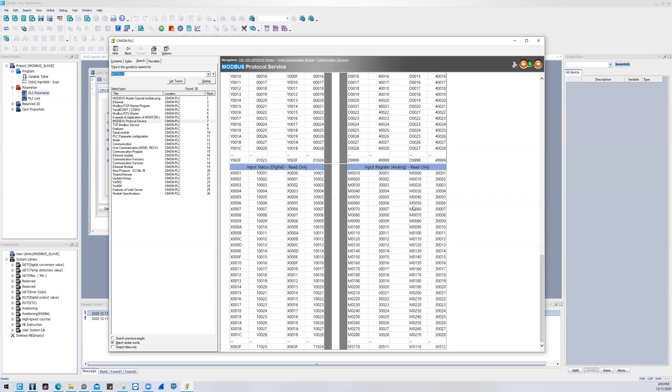The same can be said about your M's. You just have to put a 0 at the end of the register, and that will declare the word form of that register. So if I target 300008, that means I'm looking at the register M70, the word. And notice how it's just an offset of 1. So 7 maps to 8, 8 maps to 9, 9 maps to 10, and so forth.